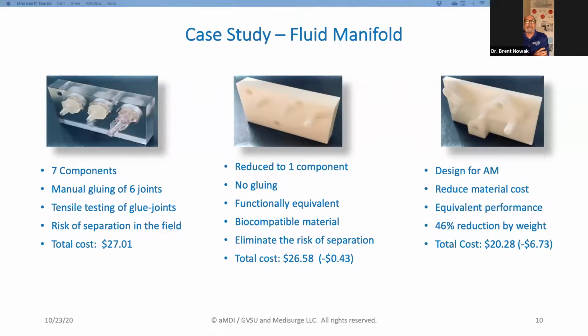Well, we did a direct replacement of that design as one 3D additive part that didn't need any gluing. It's functionally equivalent. We're using biocompatible materials, so you no longer have the risk of separation. We dropped the cost only 43 cents to $26.58.